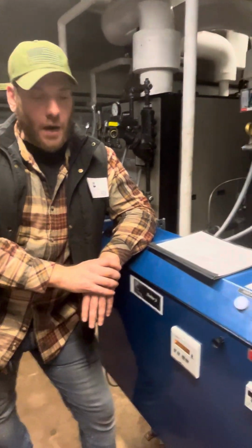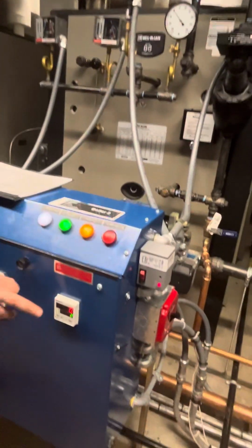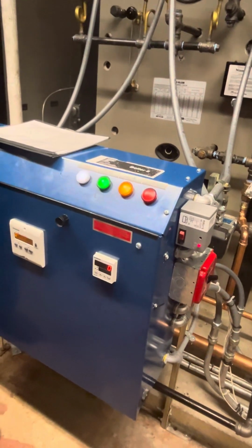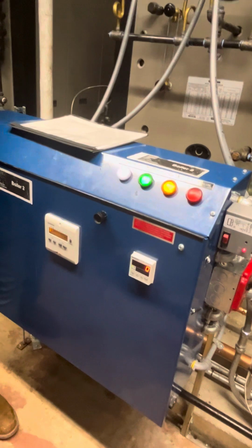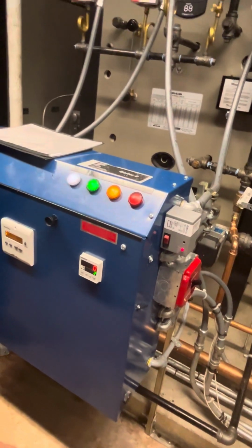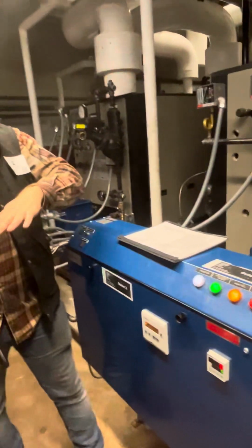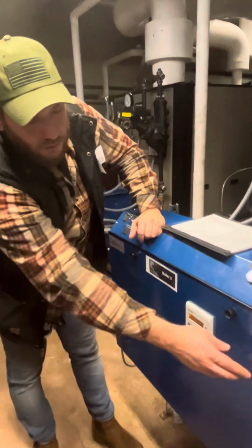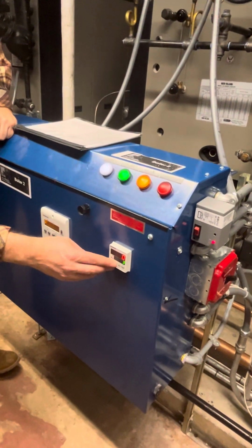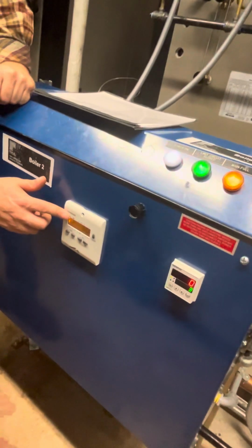Primarily, we want the set point to modulate the burner to try to maintain steam pressure. We don't want the burner going up to 5 psi, shutting off, and then cycling on and off. So when it starts getting around 3 psi, you can start slowly bringing the burner down to low fire, and then let it simmer there and maintain pressure. For now we're at 100%.